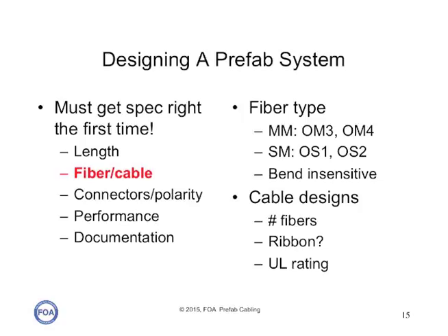You've got to choose the right kind of fiber and cable. If it's multi-mode, it'll probably be OM3 or OM4, and for single mode, OS1 or OS2. You may want to specify bend-insensitive fiber so you can have no worries about putting stress on the cable with bends as you install it. The cable design has to specify the number of fibers, whether it's ribbon or distribution type cable, and what UL ratings are needed for the cable depending on where it's going to be run inside a building.